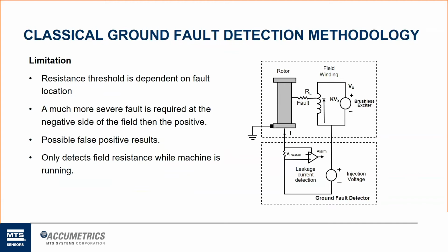So a good field, when it's rebuilt or rewound and first goes into service, may be many tens of megohms. Most utilities are only concerned with values below 500K. It's very difficult to measure any accurate resistances over 500K ohms. It just looks like a massive open wire at that point. And as long as it's very high like that, utilities aren't concerned. They're concerned with low values of resistance.